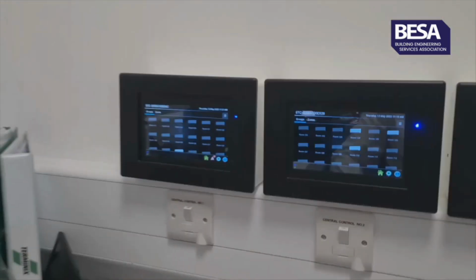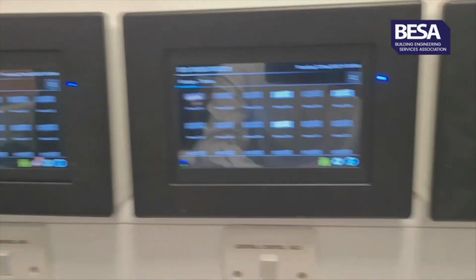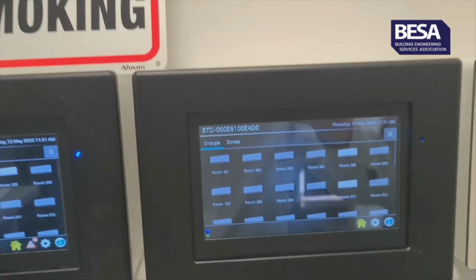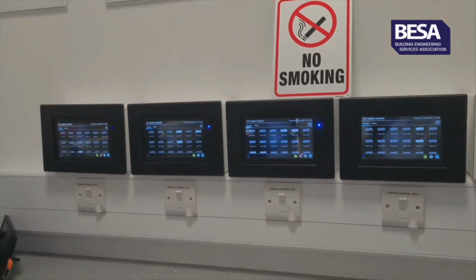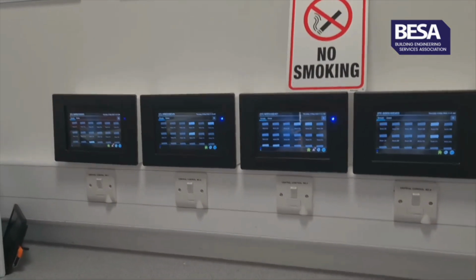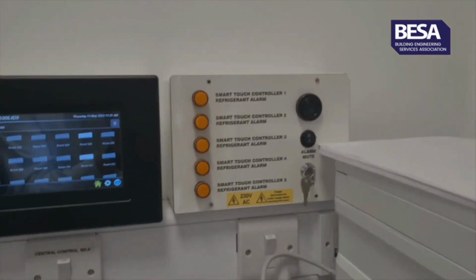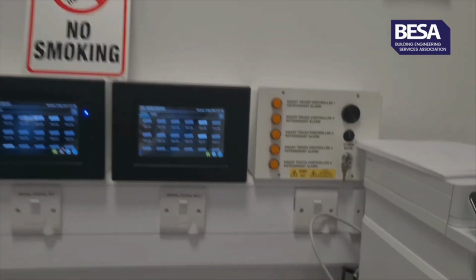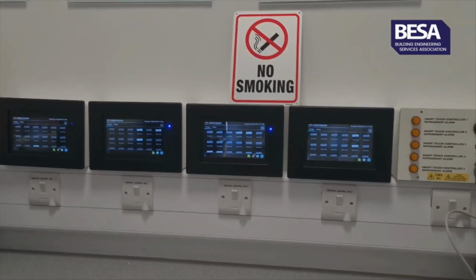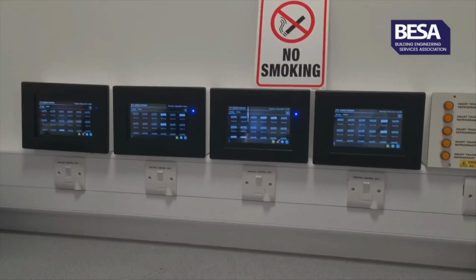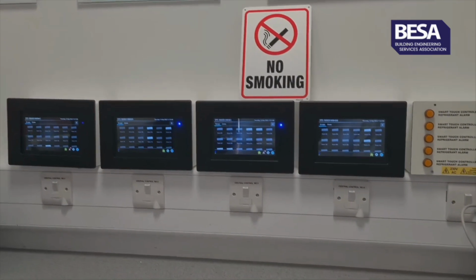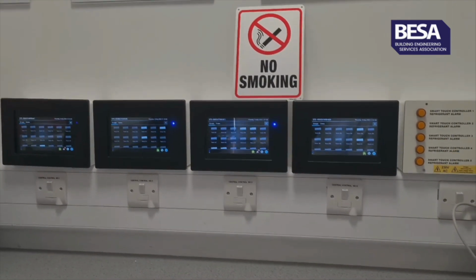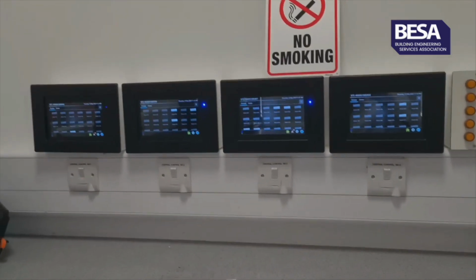And here we've got central controllers as well, so this is where the staff can interrogate the systems and see what's going on, and obviously for servicing as well. There are 180 rooms all spread across these 4 controllers. We've also got a refrigerant leak detection system. In each of the bedrooms there is a leak detection sensor which wires back to these central controllers. In the event of a leak, it will shut the system down and alert the hotel that there is an issue.